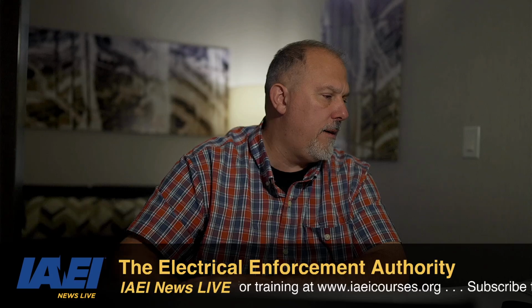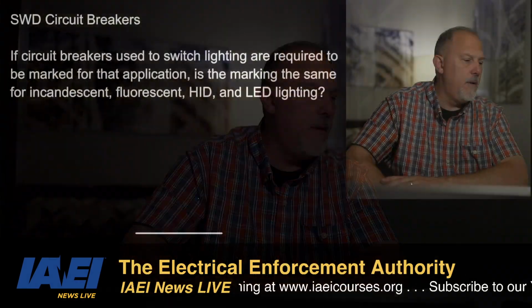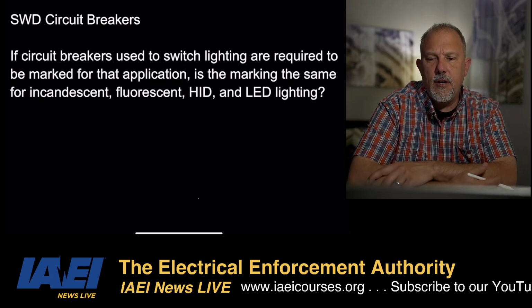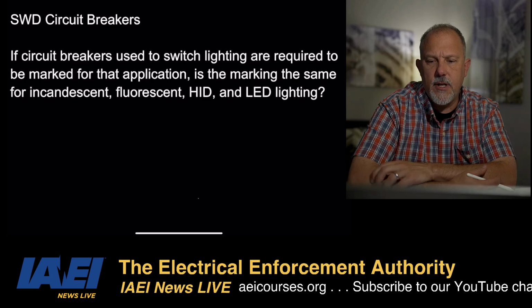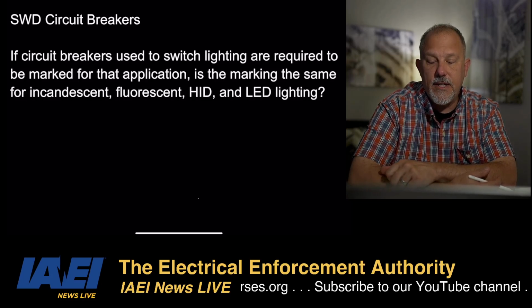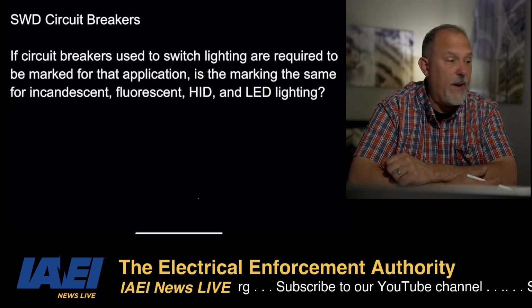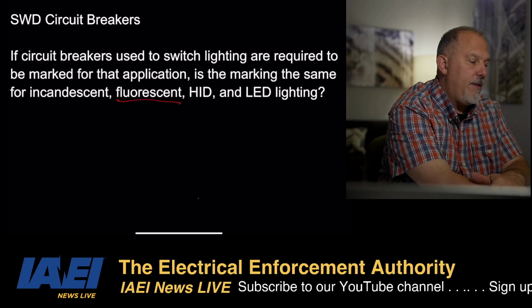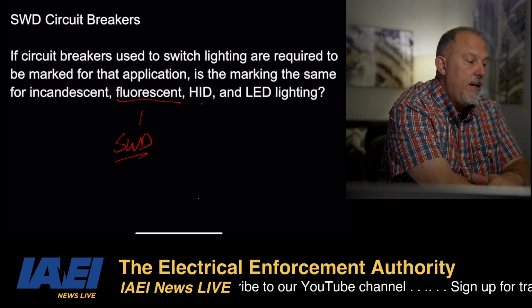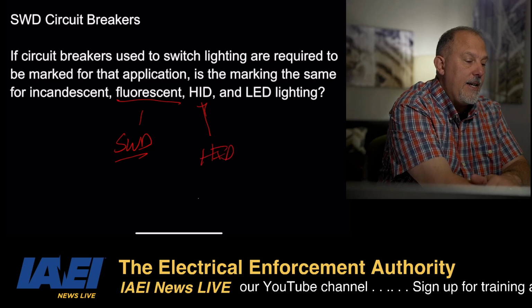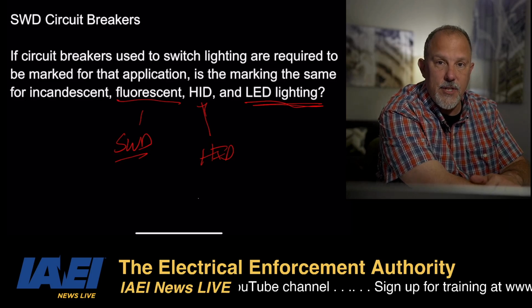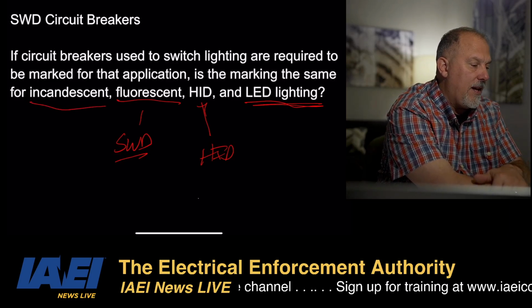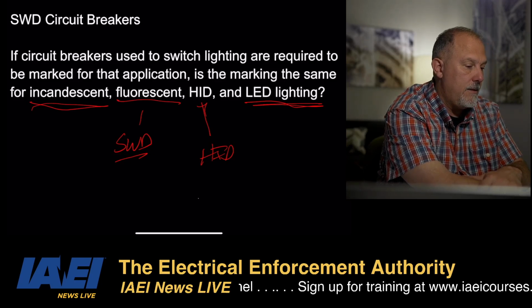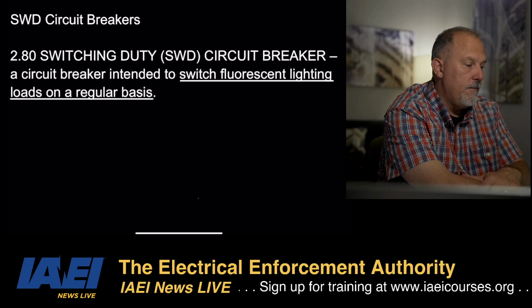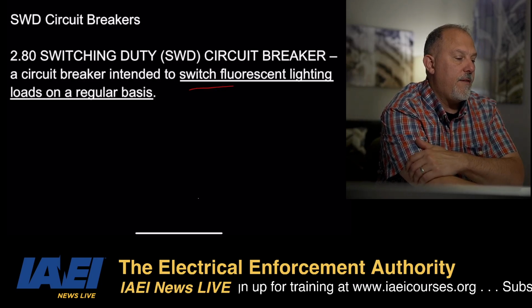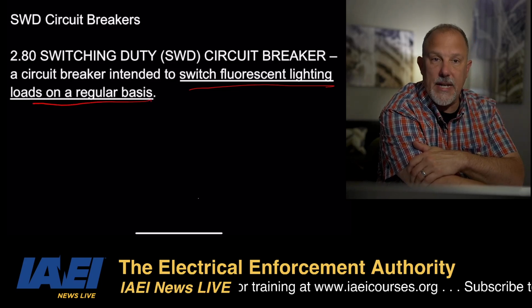All right, so what's this one? If circuit breakers used to switch lighting are required to be marked for that application, is the marking the same for incandescent, fluorescent, HID, and LED? Oh, very good question. So I know I have this is an SWD. HID is HID. I don't have a switch duty for LED lighting, and I don't have anything special for incandescent. So SWD is switching fluorescent lighting loads on a regular basis.